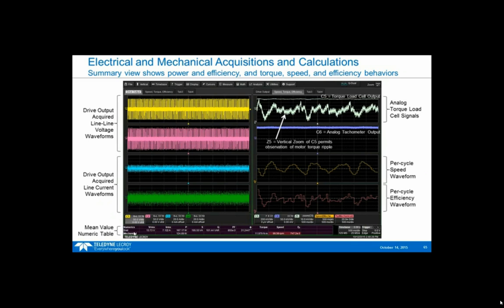This is our mean power value table right down here - it should look pretty familiar. They're looking at voltage, current, and the various power values, power factor, phase angle, torque, speed from the motor, and also efficiency. In this case they have a torque signal, which is C5 here, shown in this signal up here.